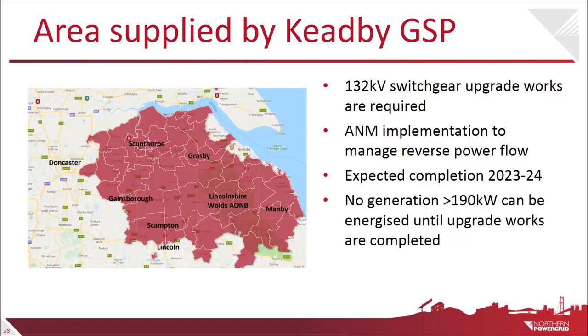On Keadby, we have to reinforce the 132 kV switchgear because of fault levels, and there is also an ANM scheme being proposed to implement. Until these works are completed, both the switchgear upgrade and managing reverse power through the ANM scheme, no generator greater than 190 kilowatt can be energized.